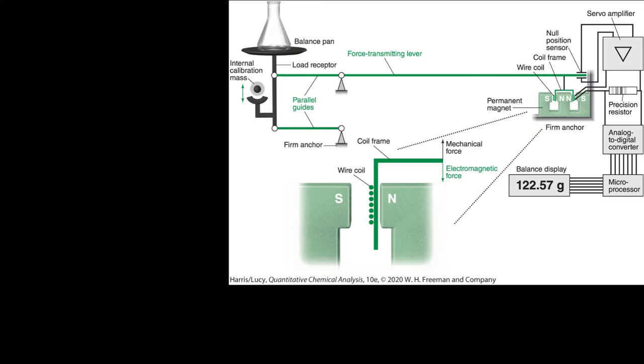We certainly have some things to worry about when we use an analytical balance. The first thing is the whole entire thing has to be level. And so on the outside of the balance, you typically find these little circular areas with a little air bubble inside. The air bubble is inside some oil, and you have to level things out. So you have adjustments on here. You can move the balance in one of four different directions to level the dot until it's back in the center again. And if it's centered and level, then it reads true.